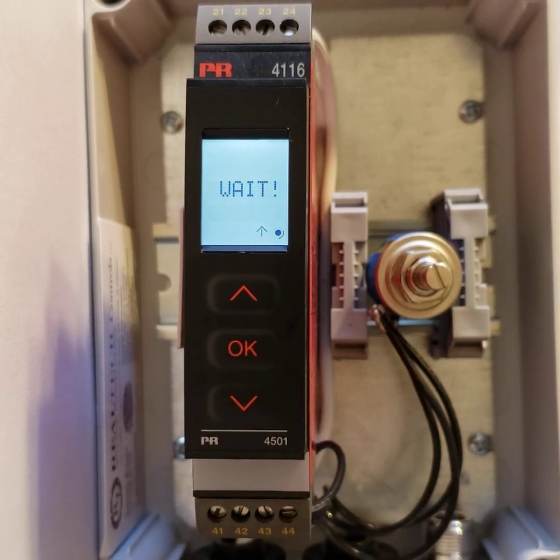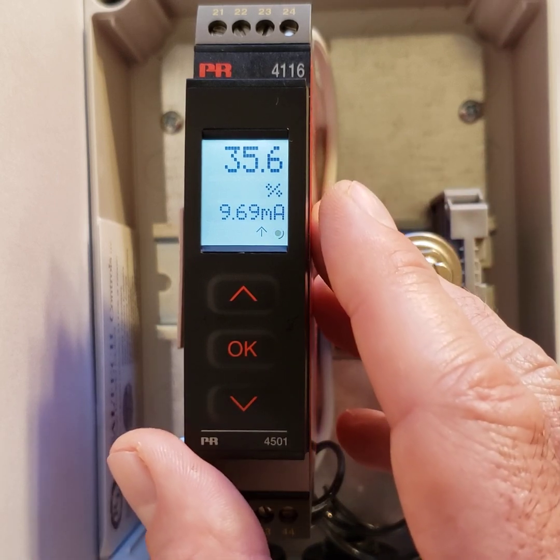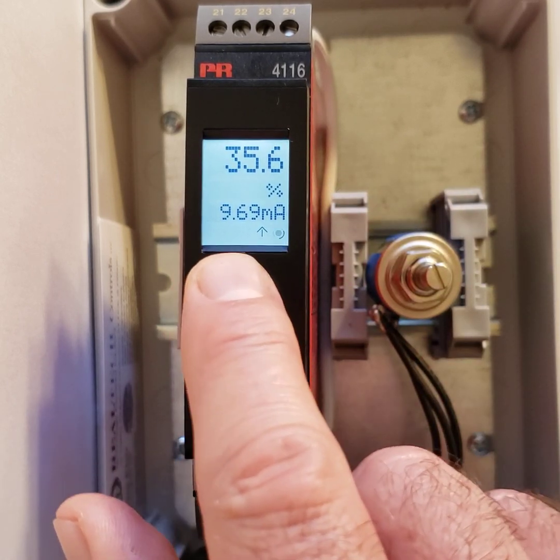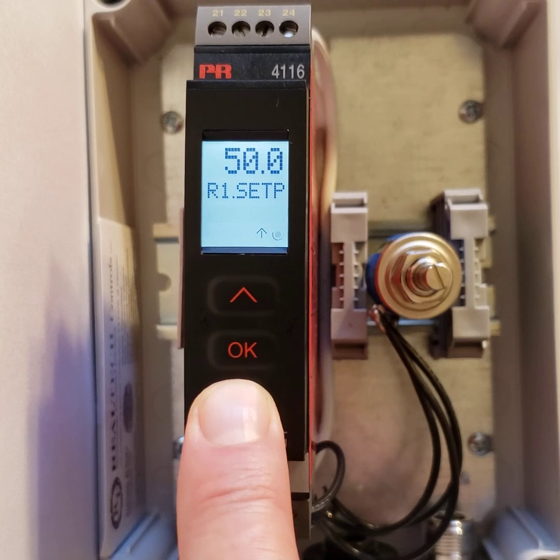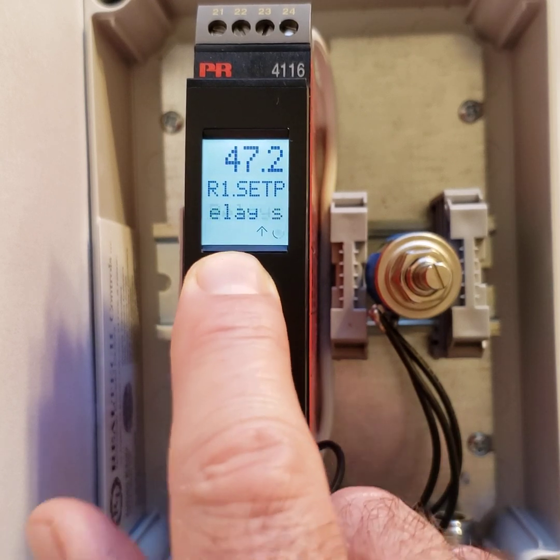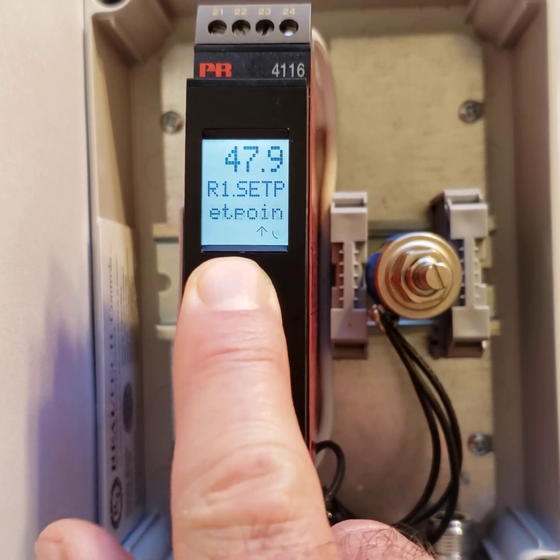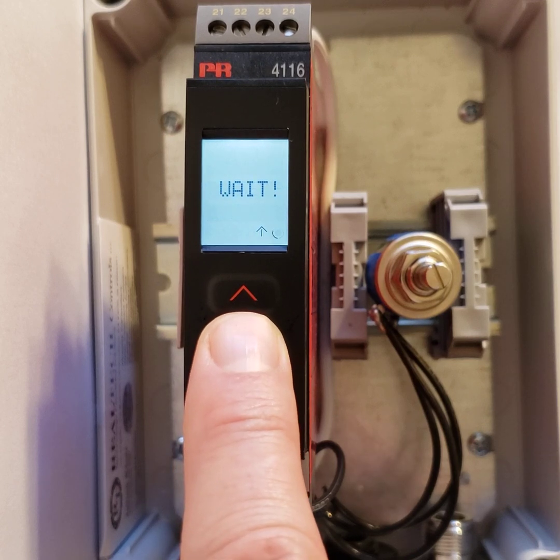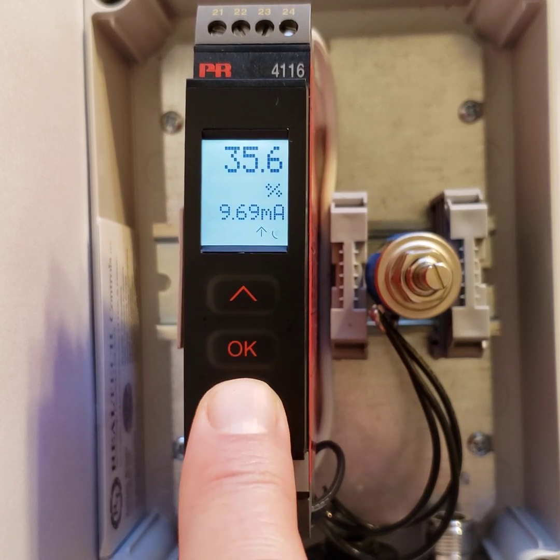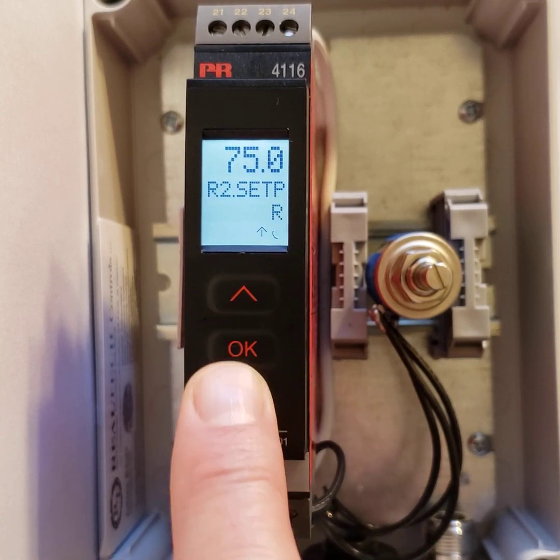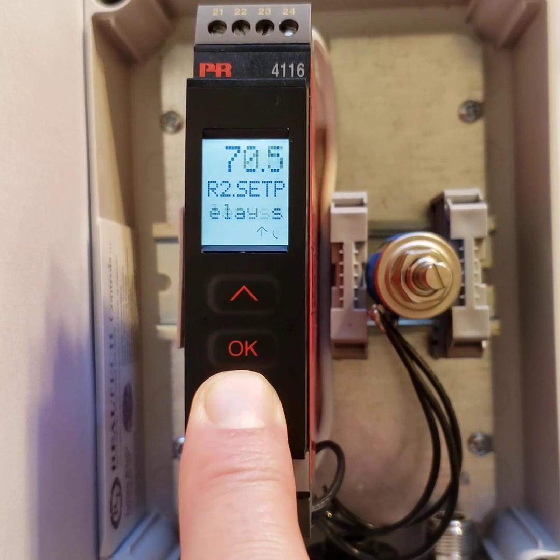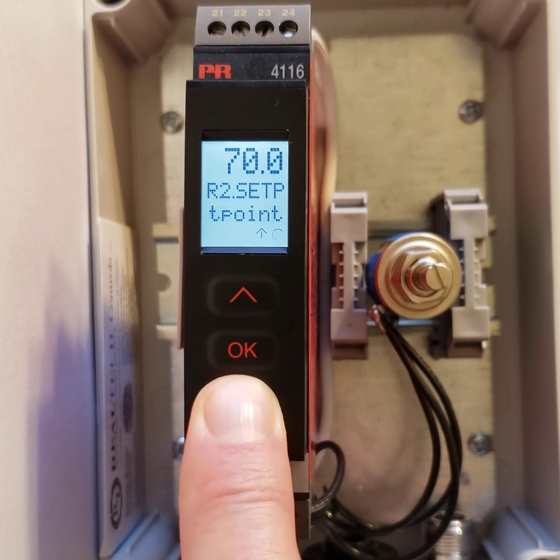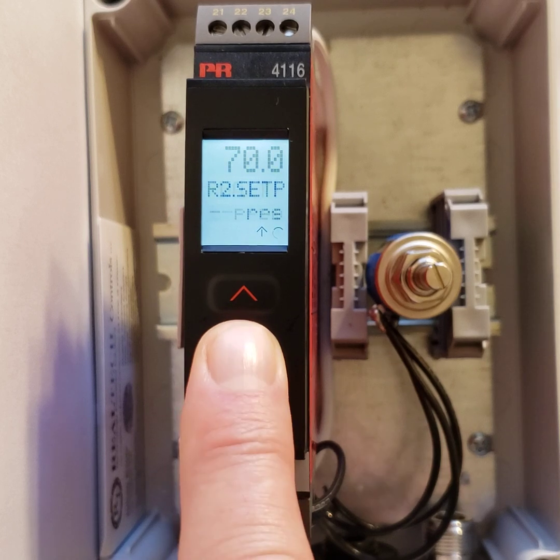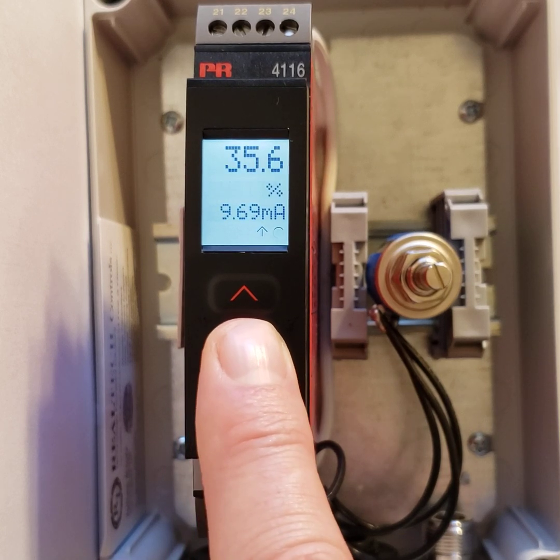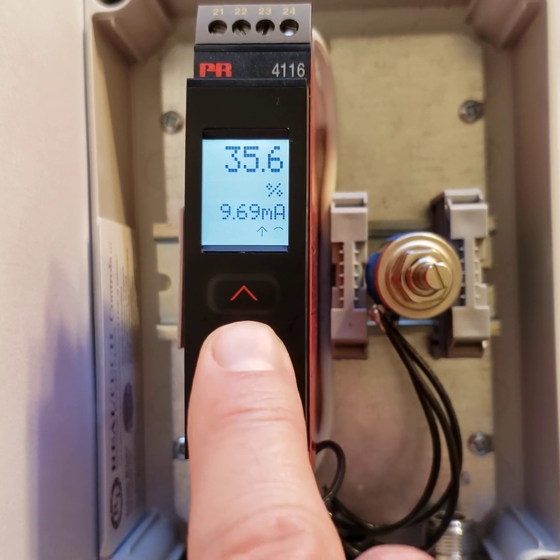So if you say yes, now if I'm in the home screen, I don't have to go into my general setup to access my relays. I can just push the up arrow and there I can set my set point or change it for relay one. And if I wanted to change it for relay two, just push down and there's my relay two. You can make that say 70. And now my relays are set at those two different values.